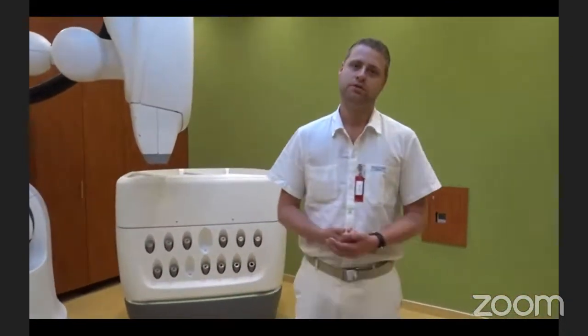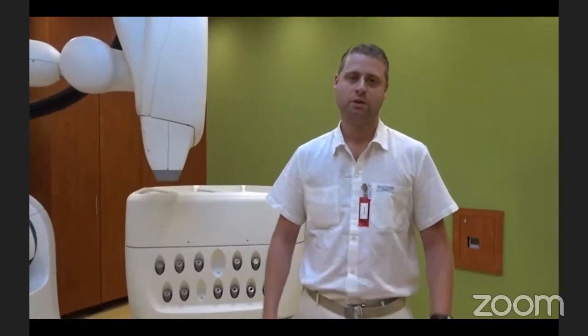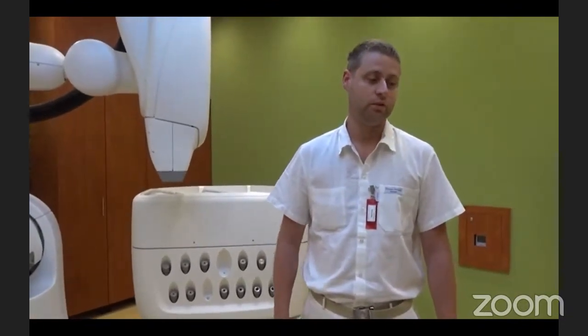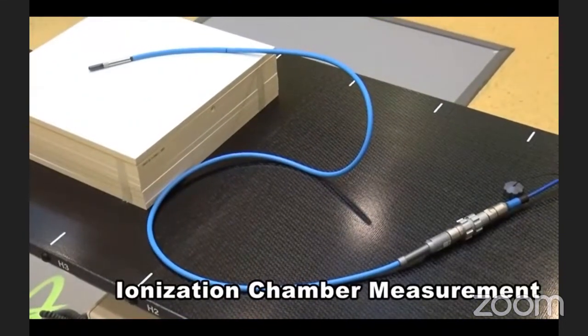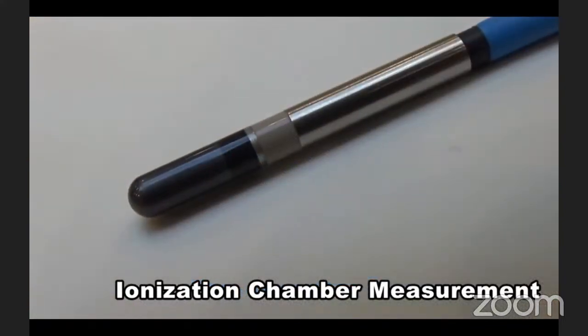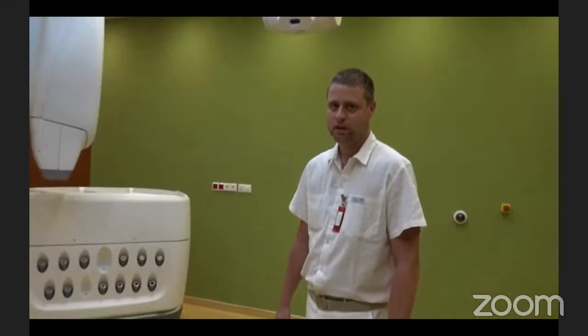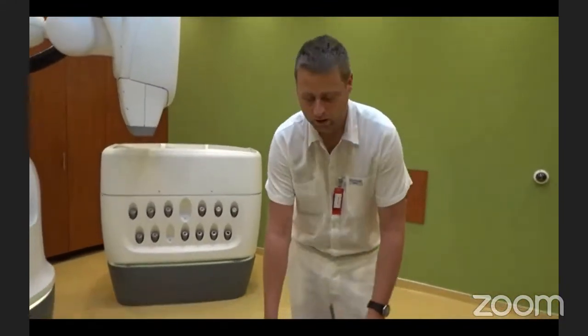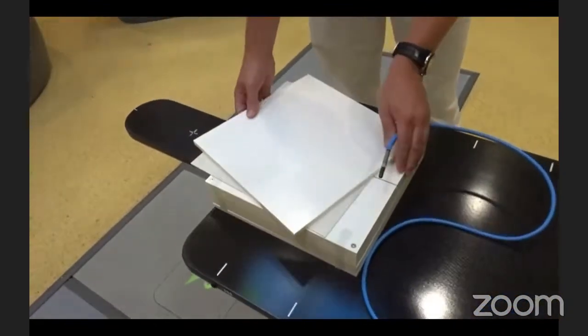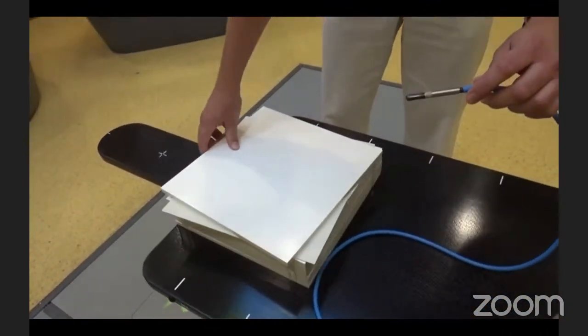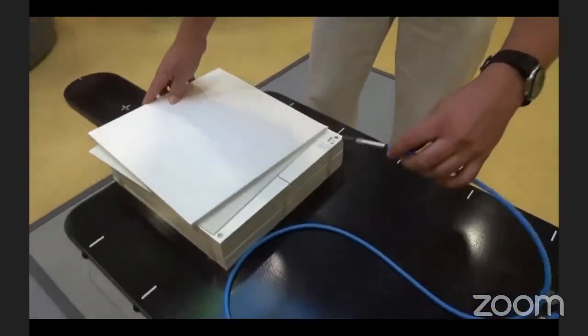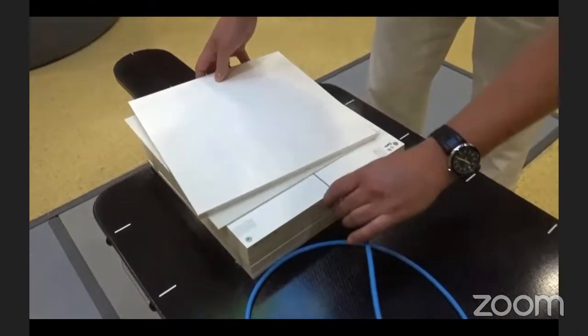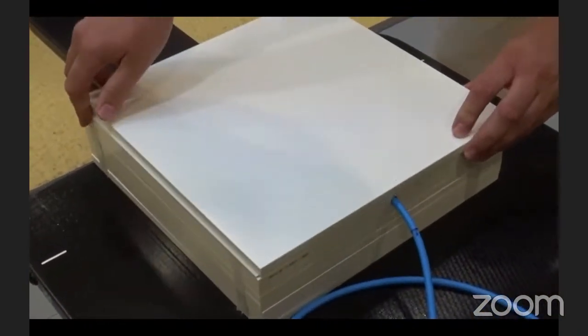On the CyberKnife we have to do strict quality assurance, and in this practice I want to show you the most used measurements that we do. First of all, I want to show you the daily QA, the ionization chamber measurement, when we measure the output of the accelerator. For output measurements, we use this solid water phantom, the so-called slab phantom. In this slab phantom, we can insert the ionization chamber. This is a semi-flex ionization chamber, and we insert it exactly 1.7 centimeters deep below the surface of the phantom.